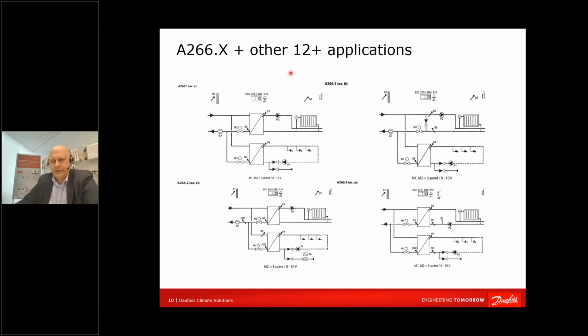It means that when you are designing the job and starting up your substation, you should select from the various applications inside that key which one should run. Some say, what is the difference between example A and example B? Generally, ECL as a controller has no capability to discover whether you have a heat exchanger in your station or a mixing shunt, or whether your motorized control valve is installed in the return or maybe the supply. ECL can read all the sensors which are connected, and it can imagine, just briefly, what it has to do.